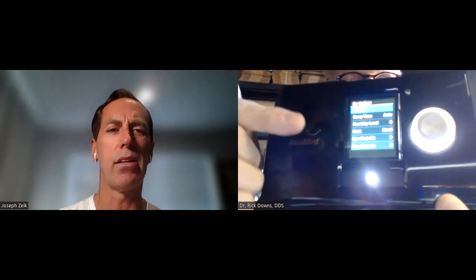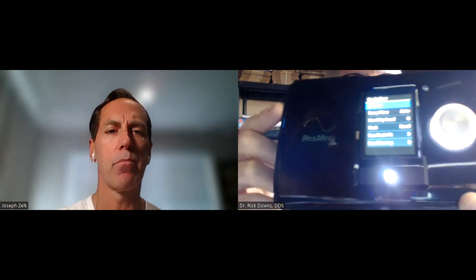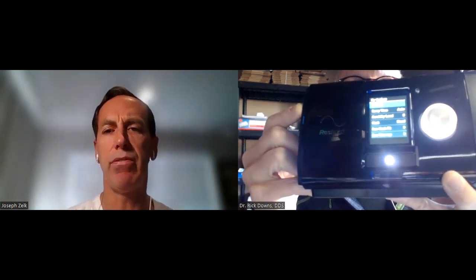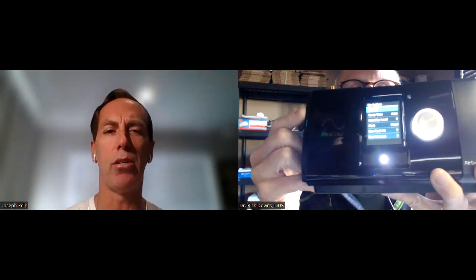So we're going to start off with an auto CPAP with a general range. We've already adjusted it. If you show them the screen there, Dr. Downs, when you press the button, maybe do the start button there on the top, you just push and hold down. You can see that it's highlighting one of the boxes there, and if you click the little cylinder, it will select that. Yep. And then if you dial it up one more time to the top one and click it, you'll see that it shows you what it's starting off with. It says right there, it's starting off on an auto setting. It's got a certain amount of time for ramp. It has a mask selection. It typically defaults to full face mask, so you want to change that to a nasal mask or nasal pillow if you don't have a full face mask.